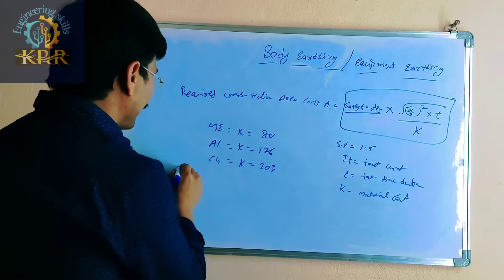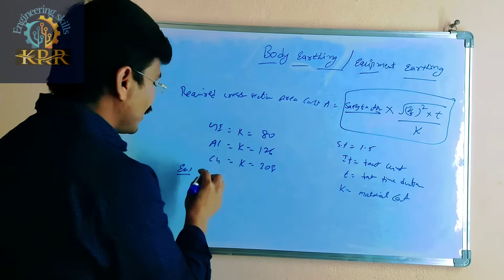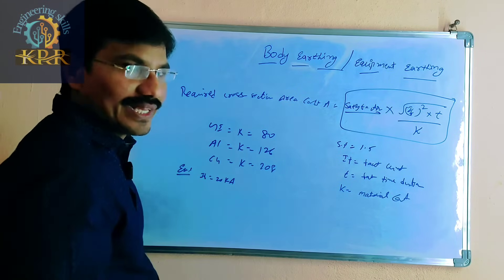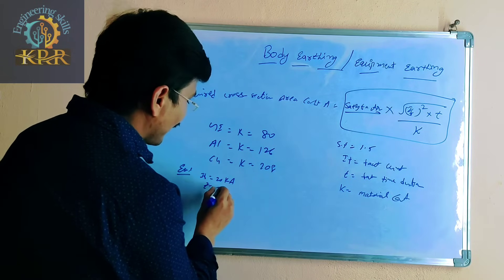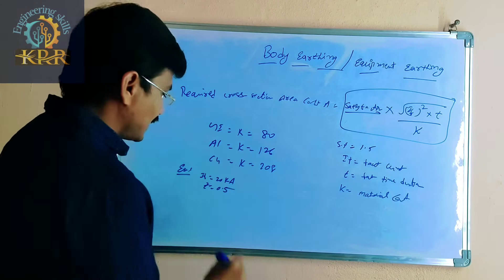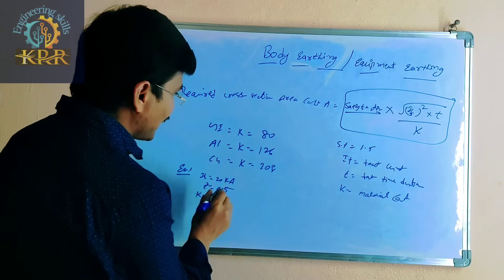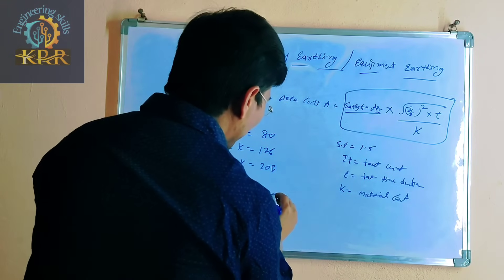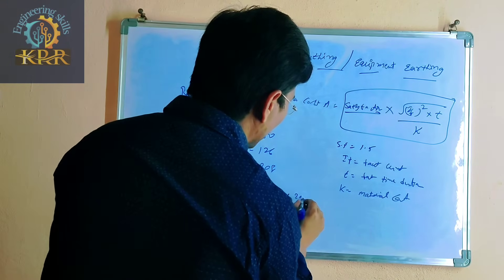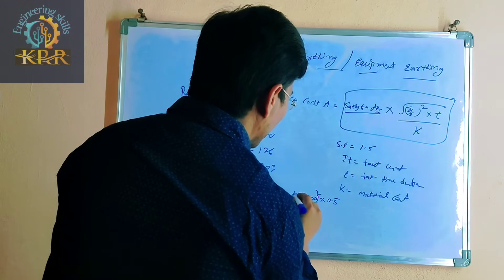For the example: fault current is 20 kA, fault duration is 0.5 seconds, and we are using a GI strip with material constant K equal to 80. The calculation is: A = 1.5 × √(20,000² × 0.5) / 80.